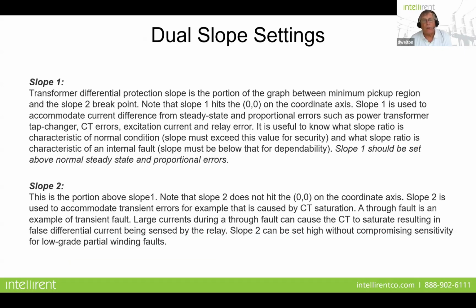Now let's talk about the dual slope setting that you see on the differential. A lot of people who aren't familiar with differential protection would ask me, why can't you just put a set of overcurrent relays? Well, you could, but that would be just one static setting, and it wouldn't account for things like CT errors. Protection class CTs are only good up to 10%. So if it's not right on the money, with just overcurrent relays, you're going to have a nuisance trip, and that's why we apply what we call a restraint slope to the settings.